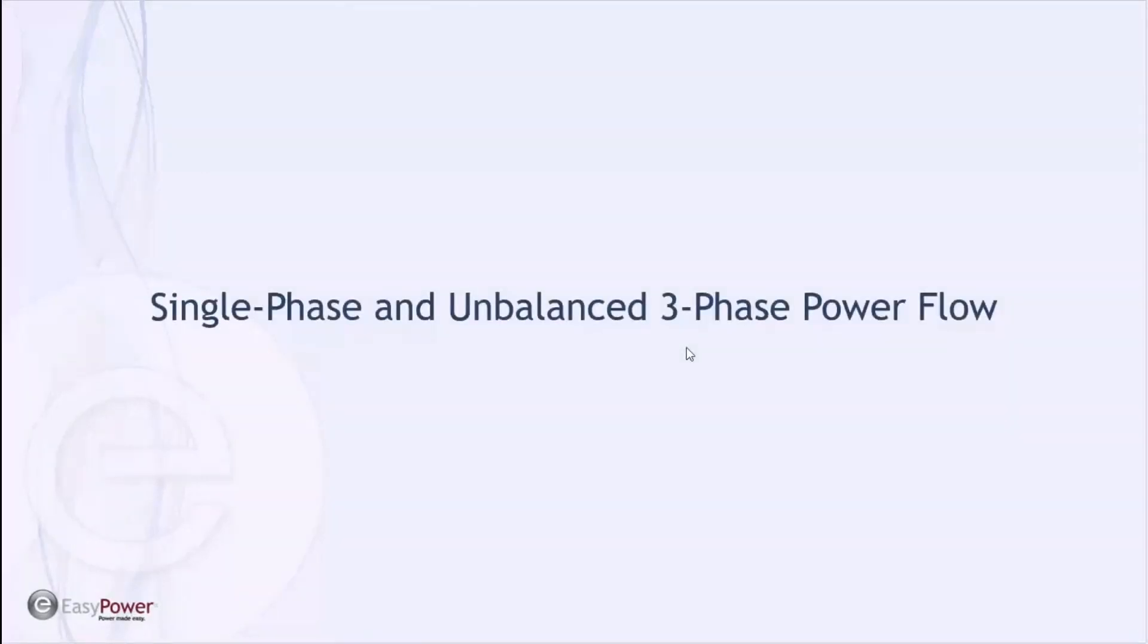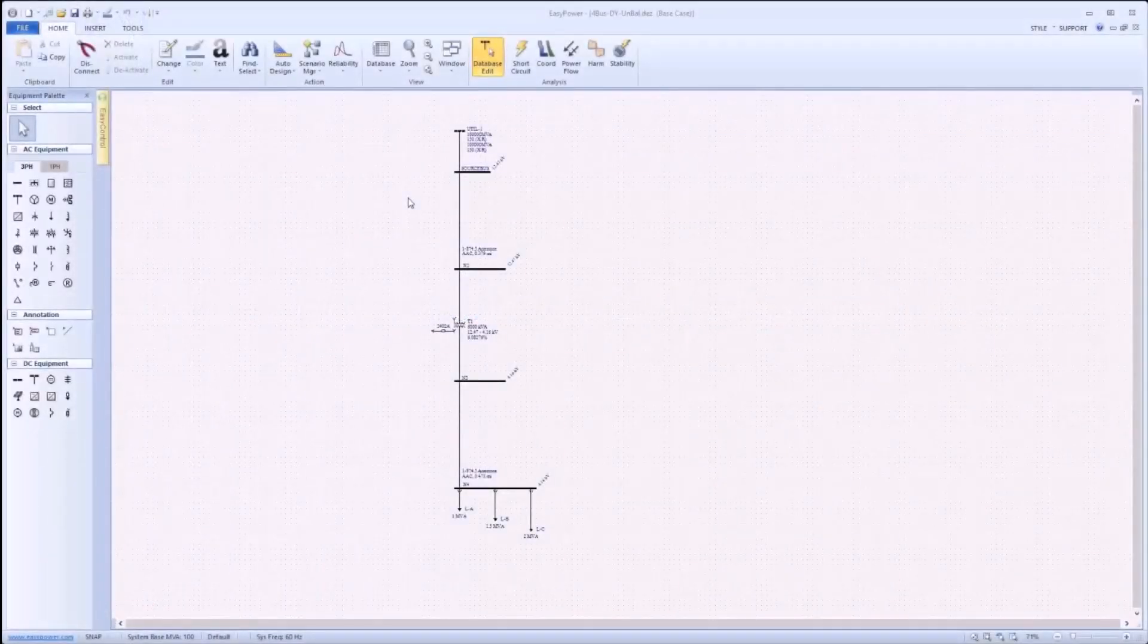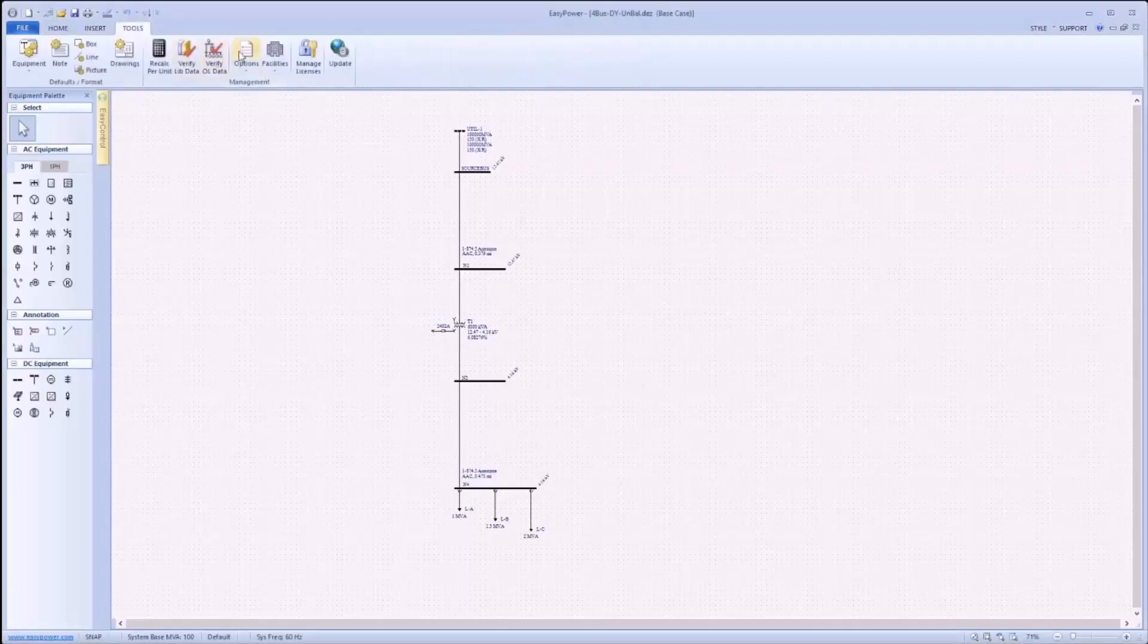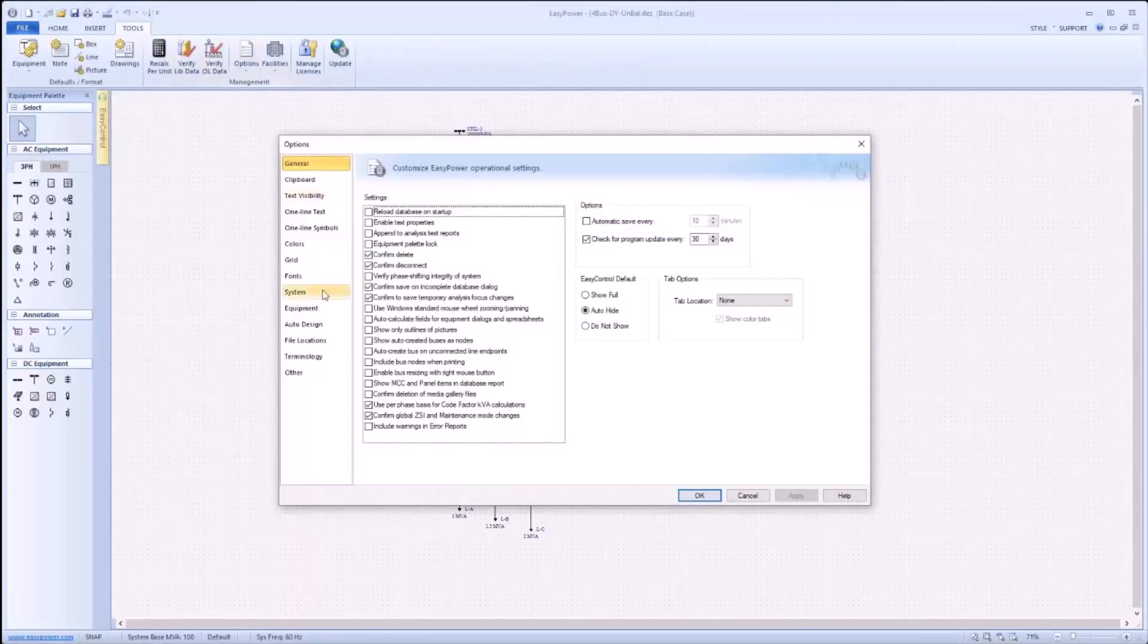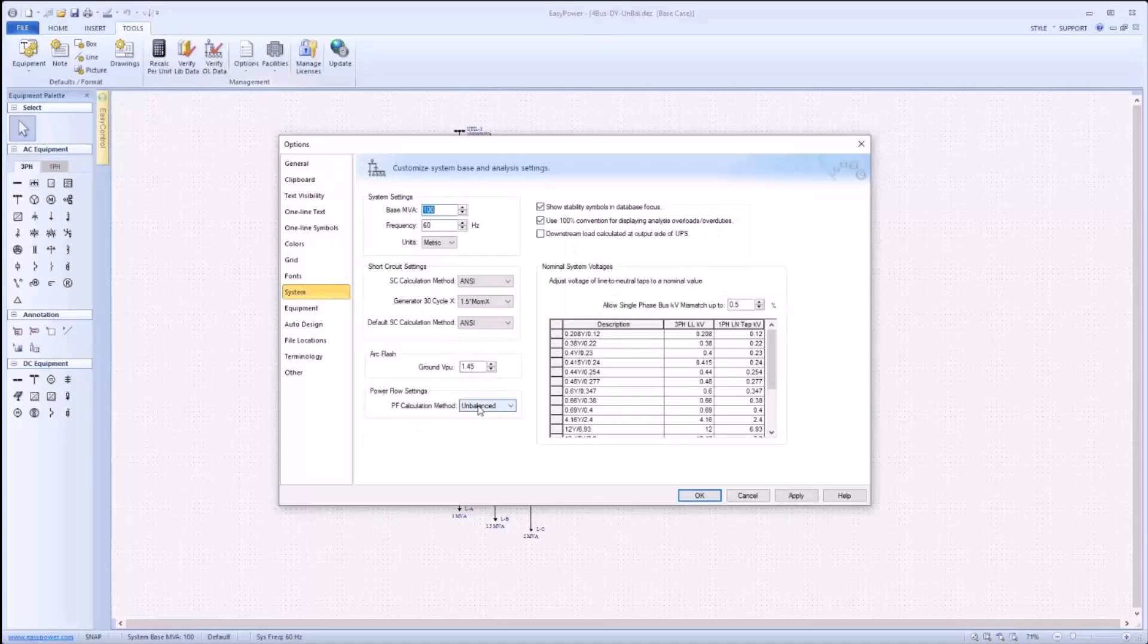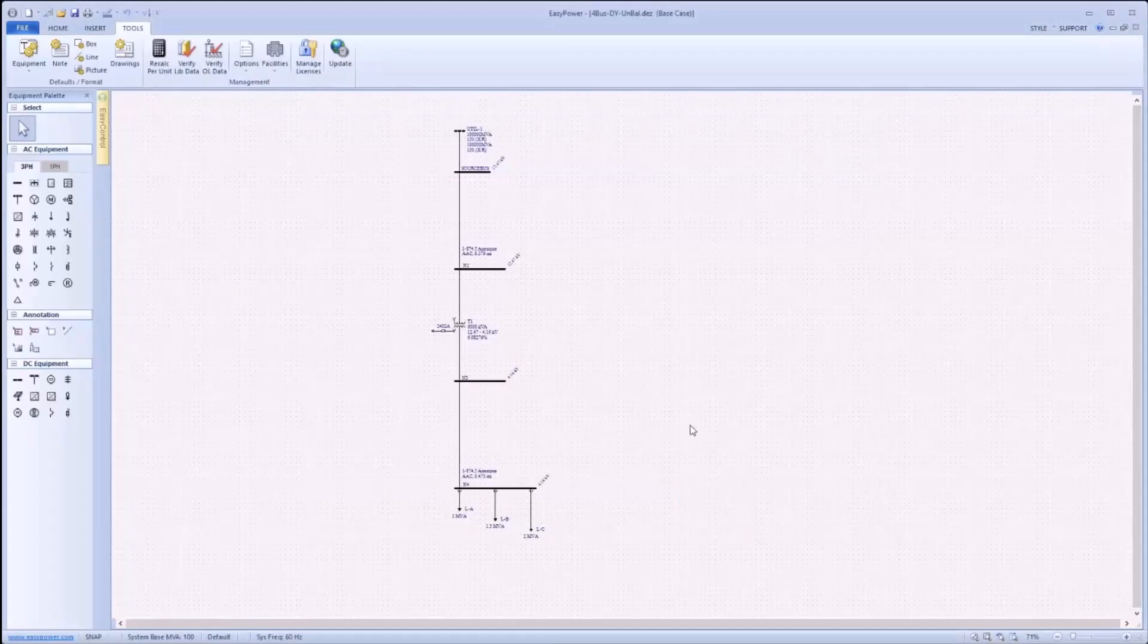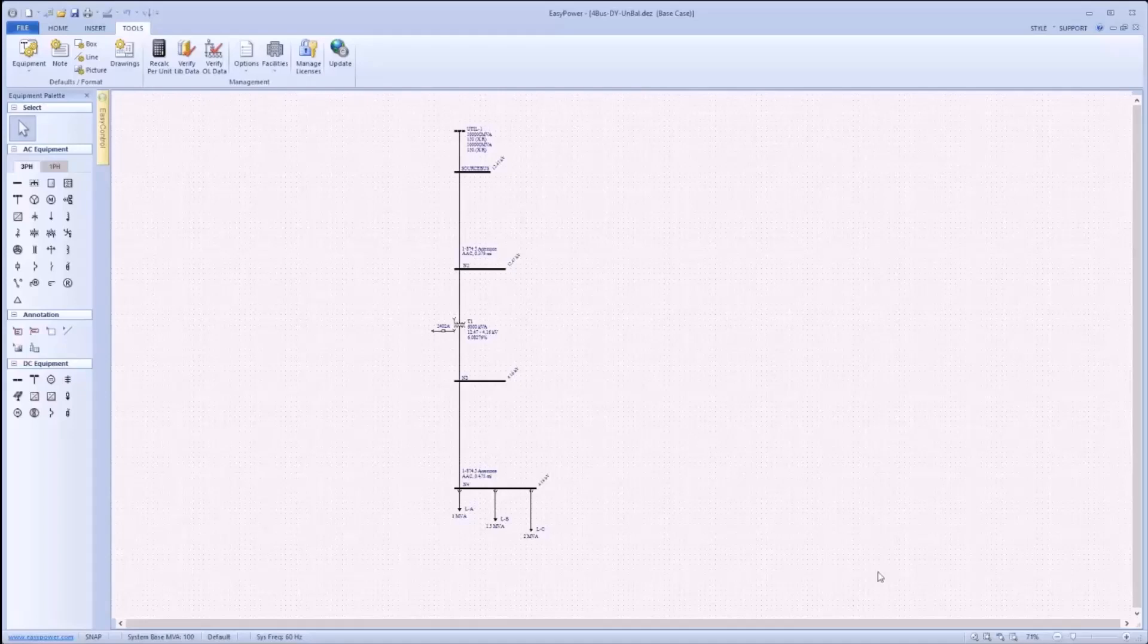EasyPower 11.0 includes support for single-phase and unbalanced three-phase power flow calculations. To enable this, under Tools, Options, System, there is a new dropdown for power flow calculation method with choices for balanced and unbalanced. Selecting unbalanced will allow for single-phase equipment modeled on the one line to be included in power flow calculations and will use the new calculation method for power flow.